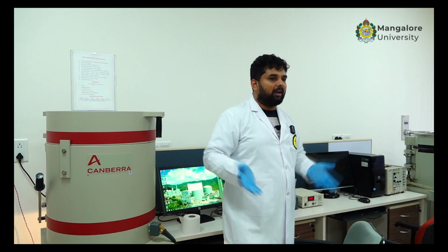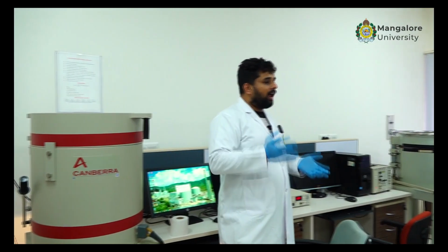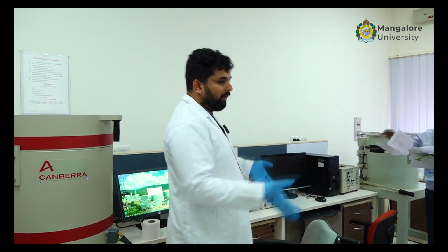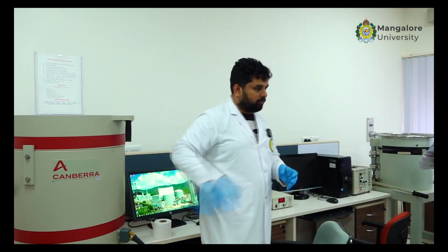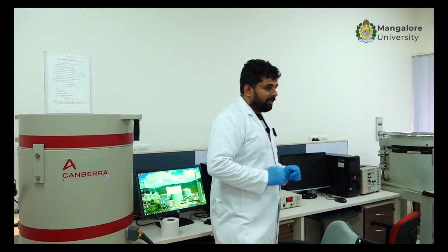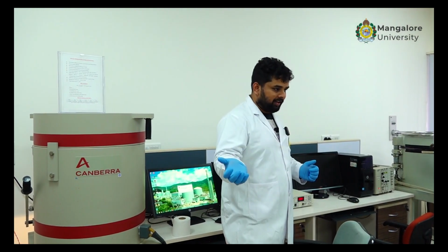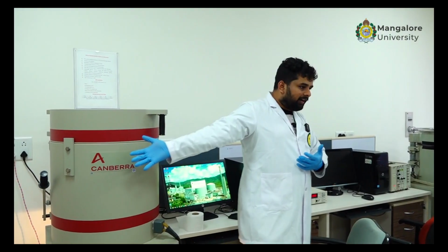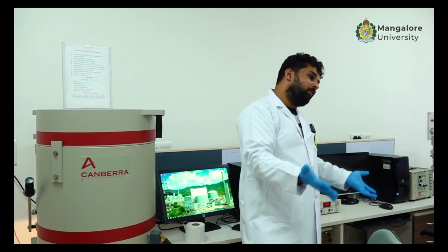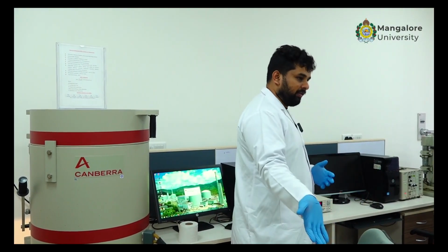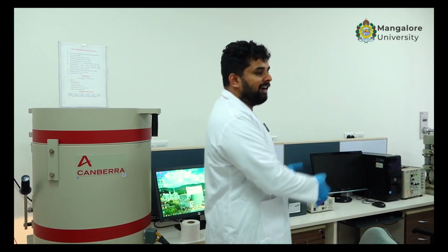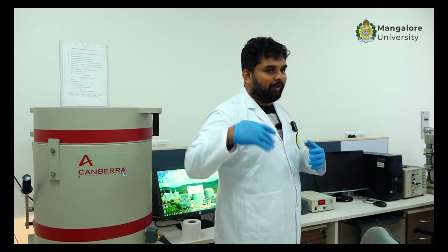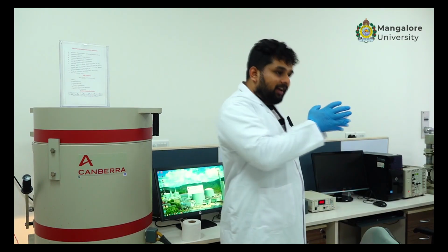So what does this energy calibration mean? I have to check whether my peak is in the right place. For example, if you are using a cesium source, this is a cesium point source, where should I get my peak? 661.6. What if I get it at 665? It might be some other radionuclide. If I get it at 609, it is bismuth 214. So then even if my sample has cesium, I will identify it as bismuth 214. Do we want it to happen? No. So we have to check whether it is proper.